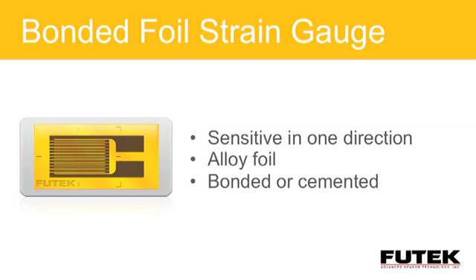In this slide, you can see a sample of what a strain gauge looks like. This strain gauge design is very typical, but the shape, functionality, and size can vary depending on the sensor requirements. The strain gauge shown is sensitive in one direction, and it's made of special alloy foils, which include Constantan and carbon material. The basic insulator backing is a polyimide or cast epoxies. Certainly there are other ones out there, but these are the two most common types.